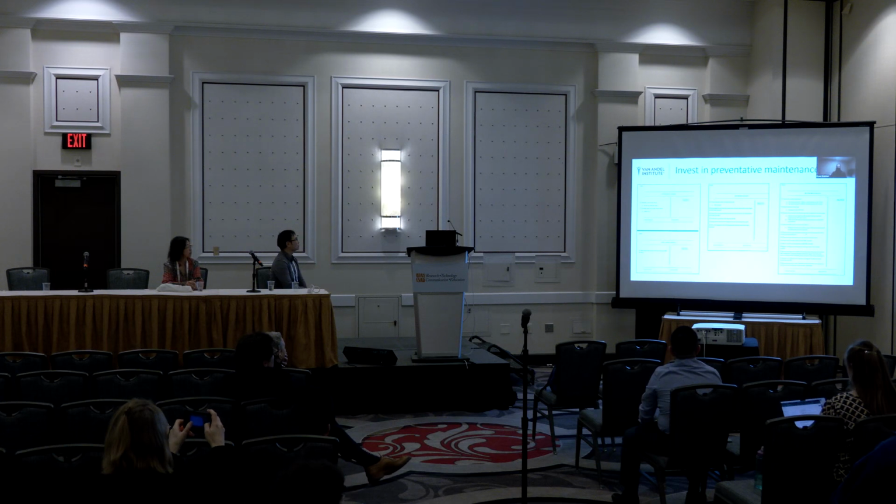These are some checklists that Abby has come up with. On the left here is a bi-monthly and every 3-month checklist of preventative maintenance items, including cleaning filter lines and cleaning ion optics. We have a weekly checklist where we clean the source, check generator pressure, calibrate, make fresh solvents, and run system suitability, which we'll talk about in a moment. And then we also have a pre-run checklist where we make sure that everything is operating at optimal capacity, that chromatography is good, the mass spec is doing what it's supposed to do, and that we check all of these things before we run client samples.